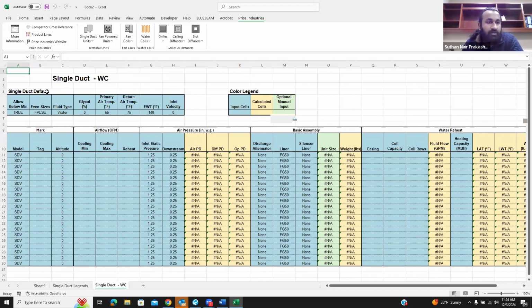So right from the top here, the single duct defaults are all default parameters for a particular building. It's not for a particular VAV box, but for the whole building. You can allow below minimum airflow to be true or false. You can have just even sizes, your fluid type water, and the glycol percentage. These are your industry standard traditional values: primary at 55, return at 75, and your entering water temperature, which is 140 degrees, or 160 or 180, depending on what you have.